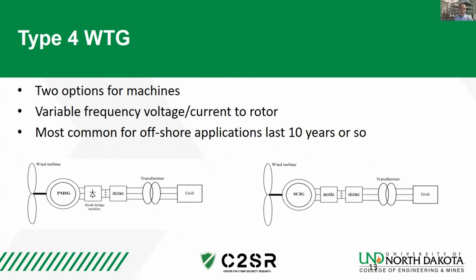For a synchronous generator's engineered control response with a closed loop control system, the time constant is generally a half second or longer. For wind or photovoltaic converters, that control response time is on the order of milliseconds, so from the power system's point of view they look like they have nearly instantaneous response, meaning their equivalent inertial response is very, very short.